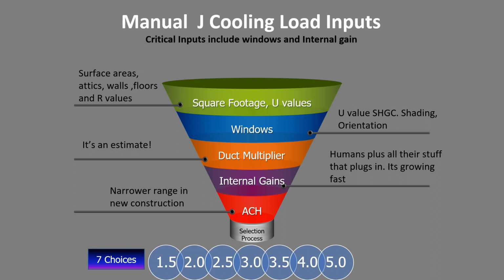It gets a little more complicated on cooling. All of a sudden we have to put up with solar coming in through the windows. So we still have to collect the square footages and the U values. Windows are critical. We need the U value, the solar heat gain coefficient, and the orientation. East and west windows affect the cooling load the most, because in the summer that's when the sun is low and just comes beating through those east and west facing glass. Duct multiplier changes from winter, especially if you have ductwork up in the attic. Internal gains, that's the stuff people plug into their house, like TVs, refrigerators, freezers, and it's also us humans. And then again on the ACH business.